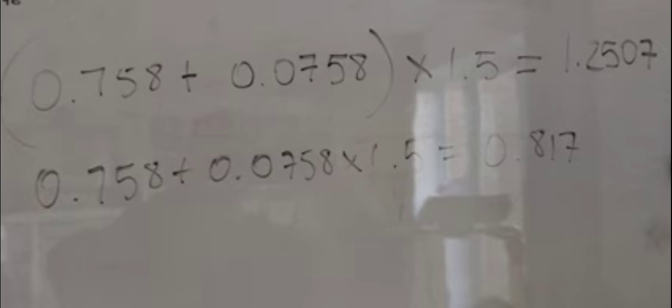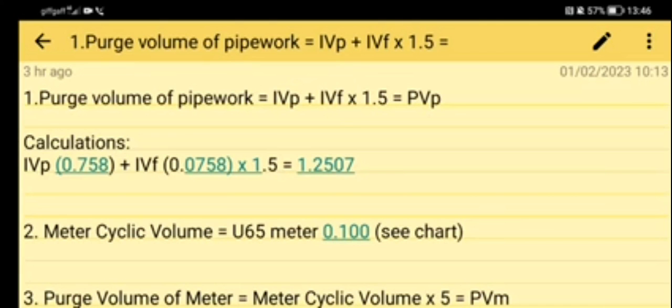I did ask someone to verify the results and they said it looked all correct, but what they didn't realize is that I made a mistake when working out the cyclic volume. In stage two, I actually got the meter volume rather than the cyclic volume. Be careful not to do that. Make sure that you work out the cyclic volume. The meter volume is there for when you're doing a tightness test, but when you're doing a purge you need the cyclic volume chart.